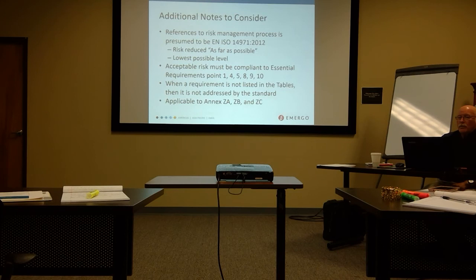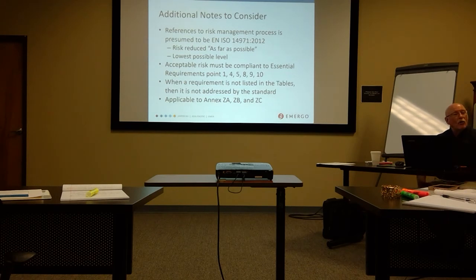Let's see, 14971 we'll touch on. There are two versions of that also. I think I've mentioned this. There's ISO 14971 2007, in effect for the US and Canada. There's EN ISO 14971 2012, in effect only in Europe. There are some changes. The two largest ones: in the 2012 European version, all risks are reduced as far as possible. The US version allows you to set a threshold and say for risks that we identify and classify at this level and below, we don't care. Europeans didn't like that approach, so everything needs to be reduced as far as possible.